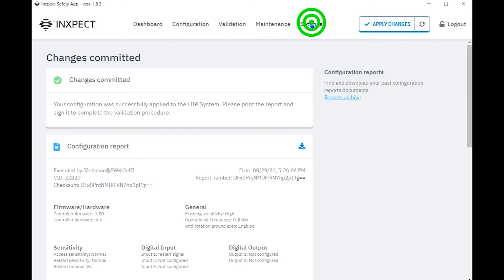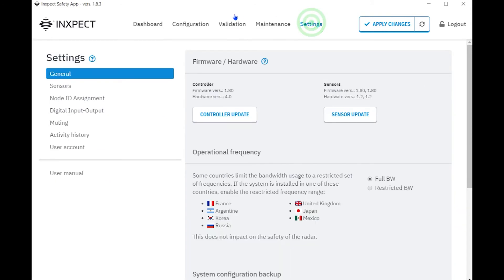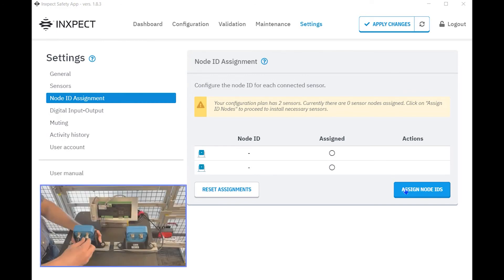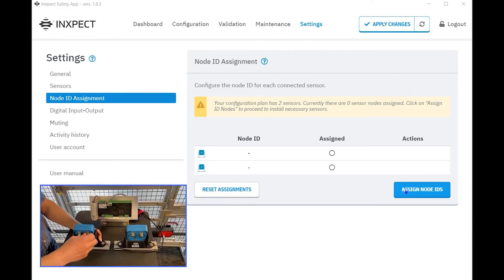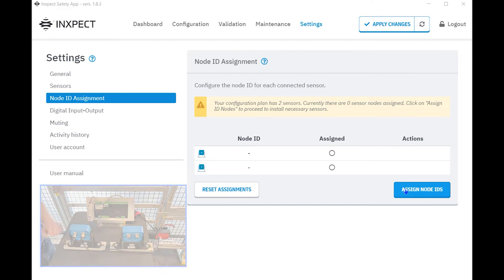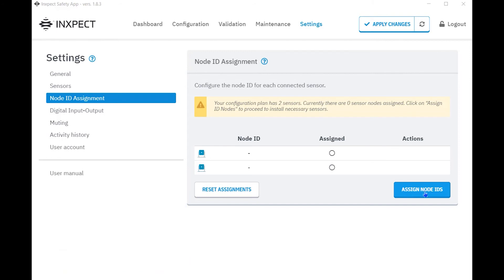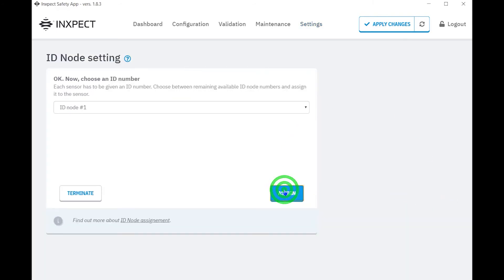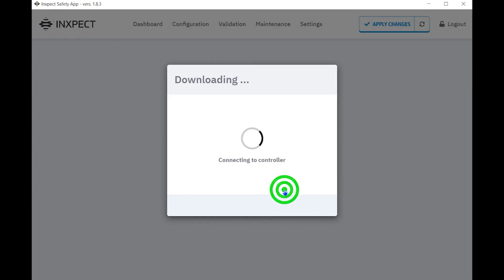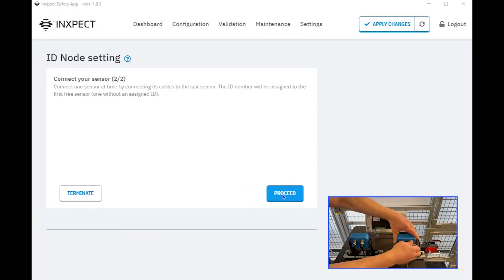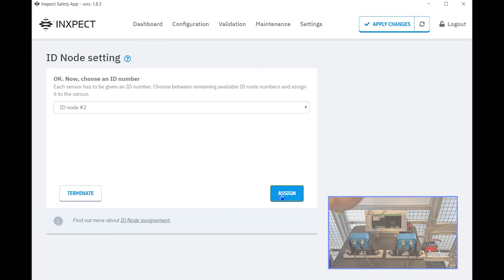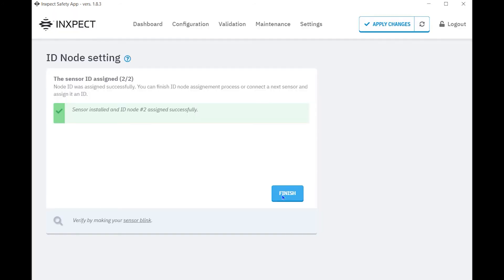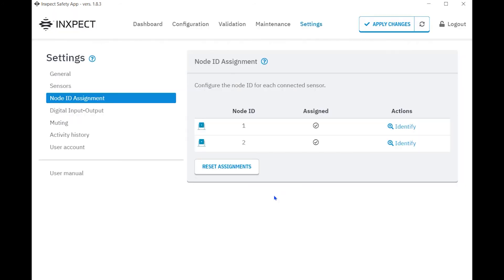This is done in the settings tab under node ID. The ID nodes link each sensor to the controller with a unique ID number. Electrically connect sensor number one to the controller with the appropriate CAN bus cable and click assign node IDs. Once the sensor number has been assigned an ID number, connect sensor number two with the appropriate CAN bus cable to sensor number one and follow the ID to sensor number two. Once completed, both sensors will now have a unique node ID number.